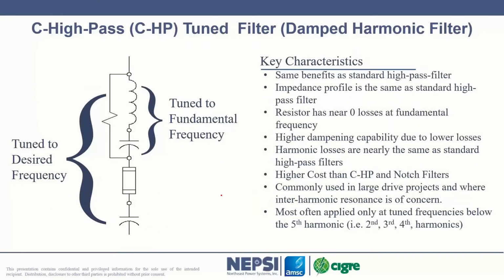A C high pass filter, incidentally, has the same exact characteristics as a high pass filter. All we're doing is shifting a portion of the capacitance from here up to there, and we're putting it inside the resistor leg here, so that we can tune this inner branch to the fundamental frequency of the system to reduce the losses in the resistor. And this becomes desirable in systems where we need to provide a lot of dampening. Okay, so higher dampening, and we get lower losses. So you pay less for the resistor because I've got lower losses. I pay less for electricity because I've eliminated the 50 or 60 hertz losses. And that's the reason to go to a C high pass type filter.